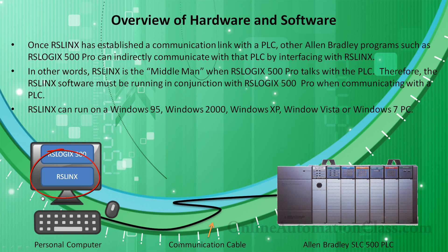Once RS-Linx has established a communication link with a PLC, other Allen-Bradley programs such as RSLogix 500 Pro can indirectly communicate with that PLC by interfacing with RS-Linx. In other words, RS-Linx is the middleman when RSLogix 500 Pro talks with the PLC. Therefore, RS-Linx software must be running in conjunction with RSLogix 500 Pro software when communicating with a PLC.